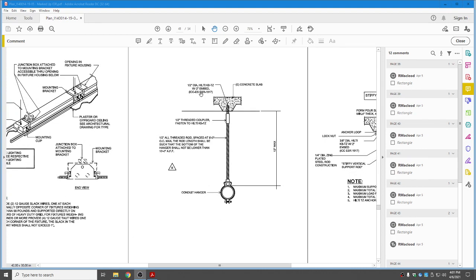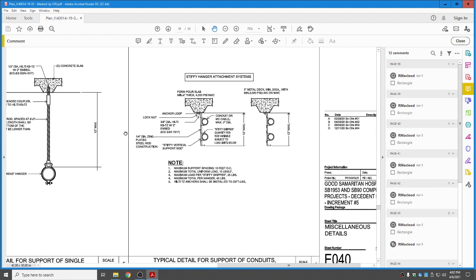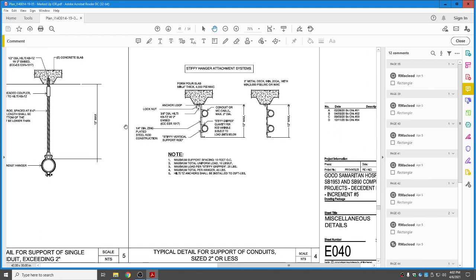And you can see at the top of that, let's take a quick look. 1/2-inch Hilti KBTZ with 2-inch embedment. And on these, this other detail is for supporting conduits 2 inch or less also. Oh, excuse me, the other was exceeding 2 inch, and this one is for 2 inch or less. Apologize. And you can see here we have a 3/8 diameter Hilti KBTZ with 2 inch embedment.